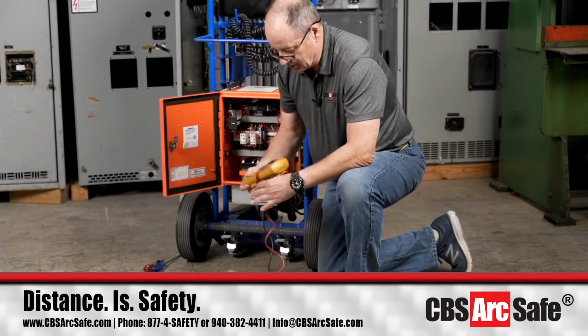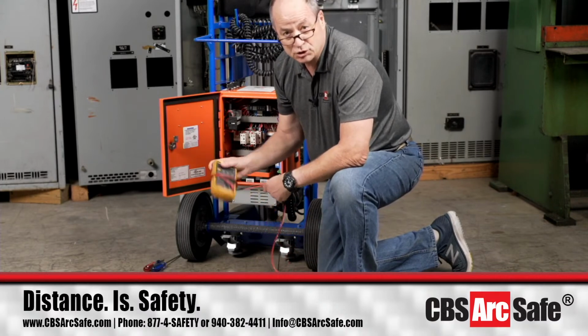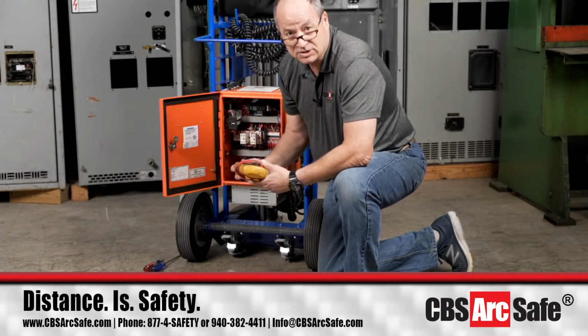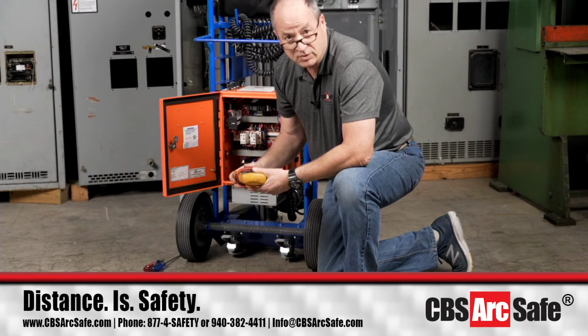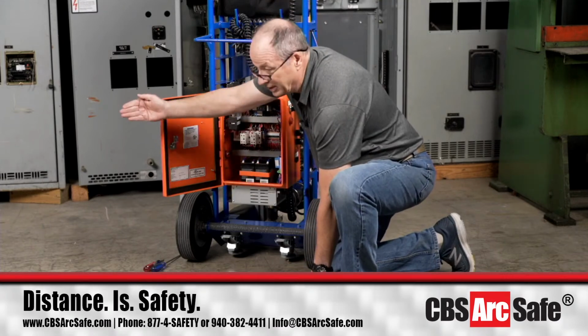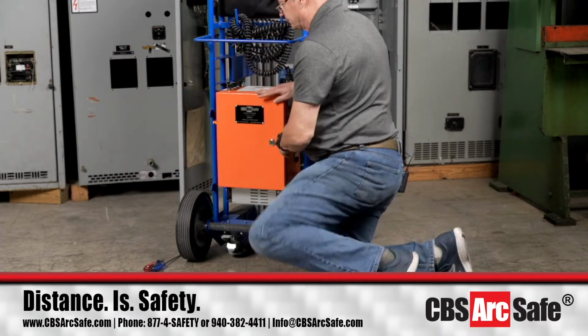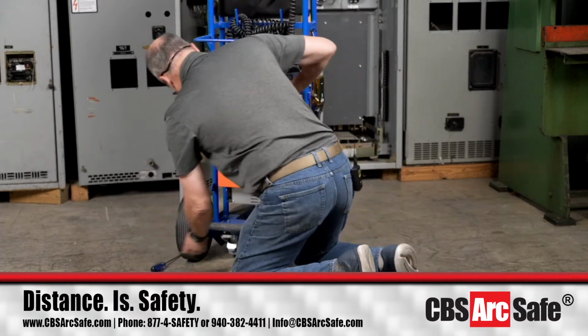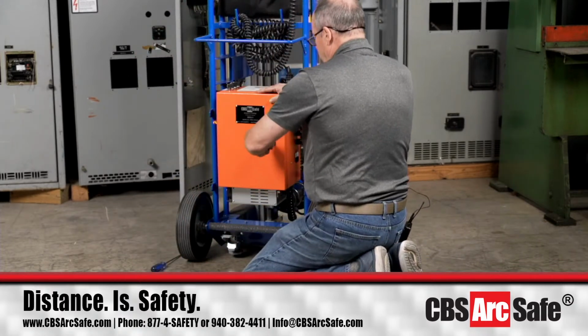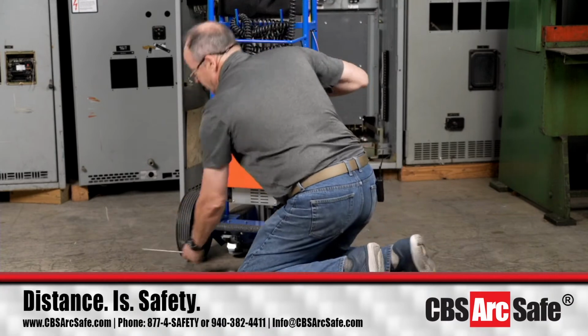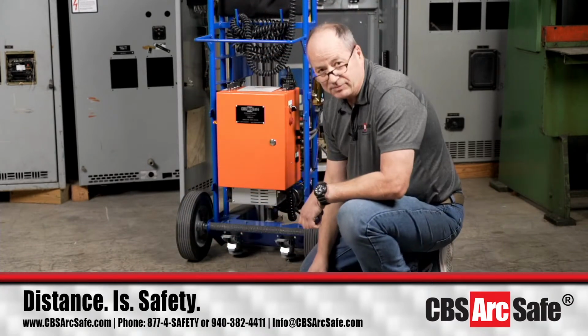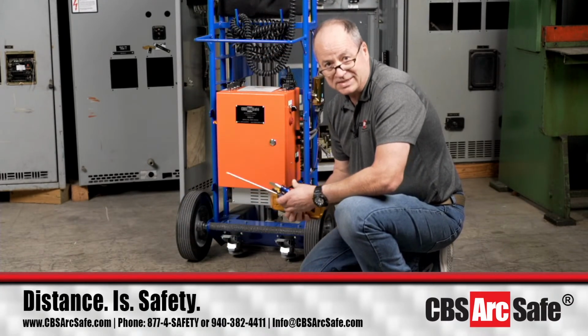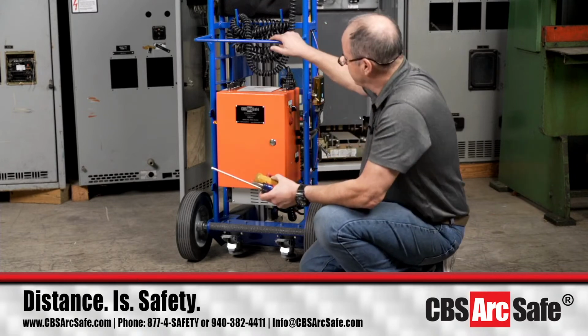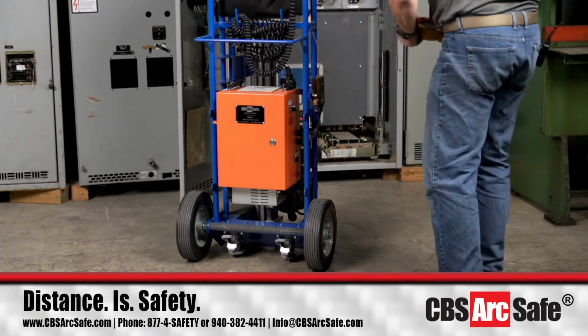If I have a set of good batteries in the unit, I should be able to rack 50 breakers in and out just on battery power for the type going in and out horizontally. If I'm using the unit for vertical racking type breakers like a G Magnablast, instead of it being 50 operations, I would probably get about 10 just on the batteries, with then needing to recharge them.